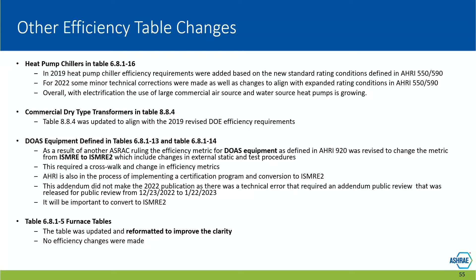We didn't do a lot of changes to furnaces as part of the ASRAC negotiation. We went from 80 to 81% thermal efficiency. May sound like a little bit, but one of the things we're very careful on commercial equipment is not getting into condensing, because condensate brings along a lot of acids and freeze problems. And a lot of the studies said it didn't really save a lot of energy because of the increased static, because fans run all the time on commercial equipment. So there's a clean up to table 5 that just covered furnace efficiencies. Next slide, please.